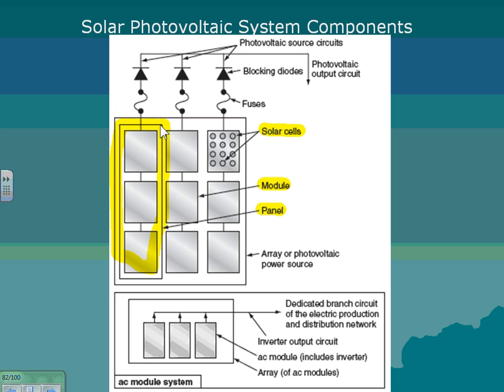What do you do? You grab another 24 panels, a string they call them, and you tie the ends of these two. Here are the ends of this string and the ends of that one, you tie them together. Now you have 10 amps here, 10 amps here, in parallel, giving you 20 amps. Means more power. And that's how they do the system. A couple of things that we always talk about, guys. There are blocking diodes. We are DC here, by the way. What you're looking at is DC.